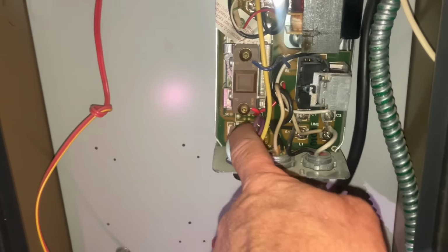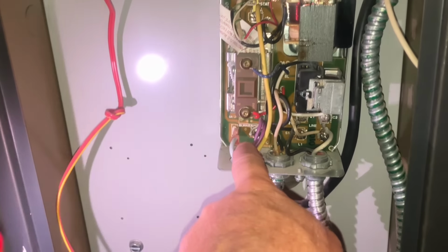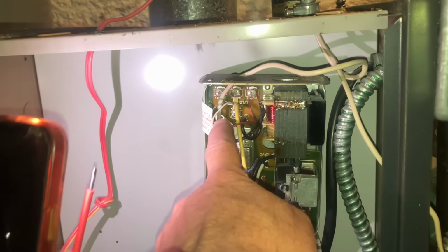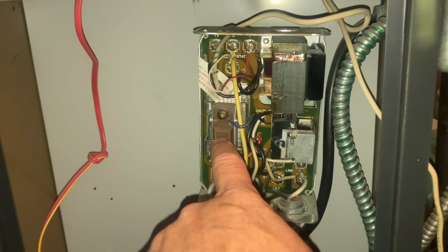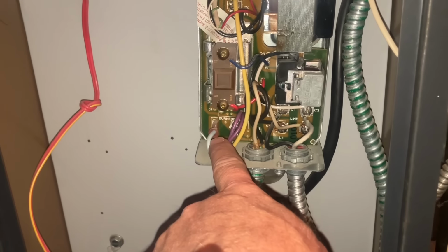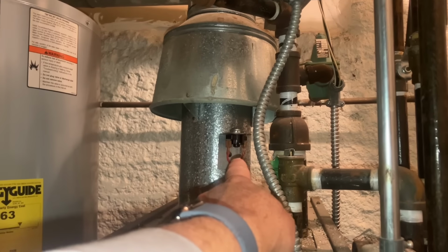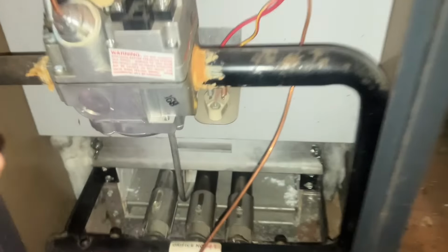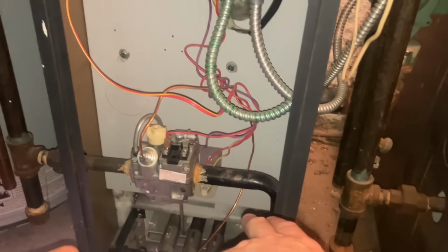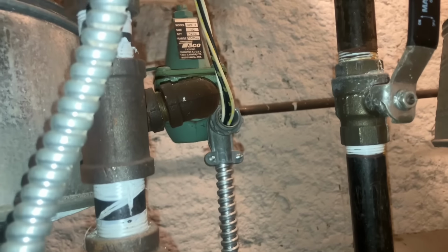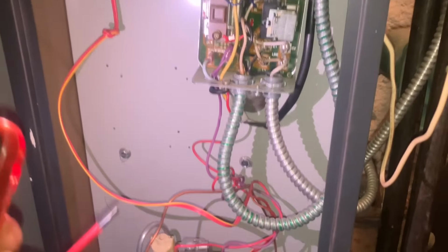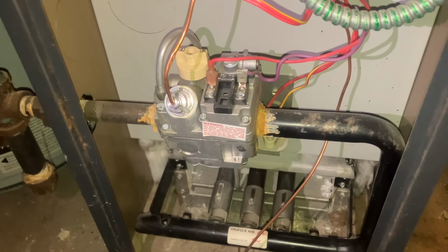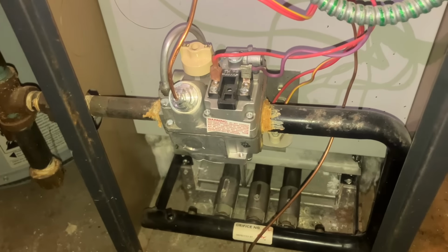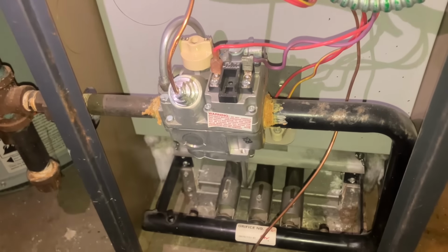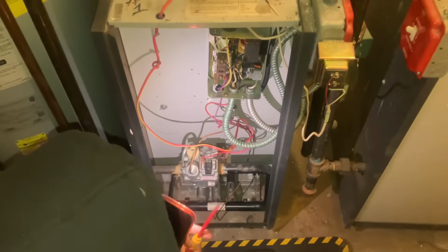On the other side here, we have burner circuit. That's 24-volt burner circuit. So when there's a call for heat, TT energizes here, closes that thermostat relay, as long as the temperature is below what this is set to, then the burner circuit gets 24 volts. That burner circuit is going to go to the blocked vent switch. The damper is going to open. If there's a rollout switch, which there is one right there, and as long as that's okay, all three of those safeties are okay. And if there's a low water cutoff, which there's not on either one of these boilers, wow, look, even the vent damper wiring is just hanging out like that. It's crazy. So as long as all the safeties are closed, the gas valve will get 24 volts, and if the gas valve is getting 24 volts and the pilot is on, the main burner is going to open. So let's flip the power on.